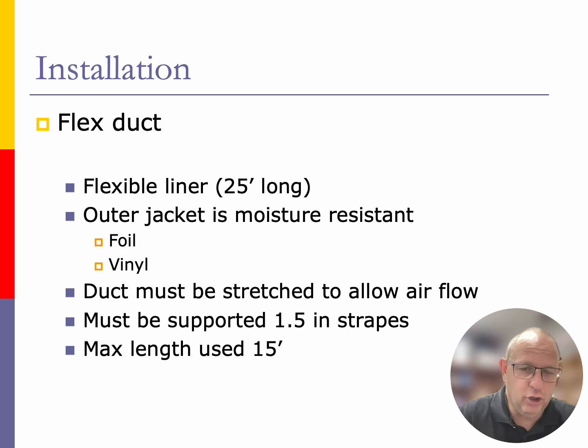So, not good. We're starting to get rid of the vinyl outer coating that's on our flex duct and starting to go with all foil back insulation that's on there. And I would have to say I prefer the foil back because it's easier for me to take my insulation that's around my rectangular duct and transition it into the foil jacketed flexible liner that's out there.